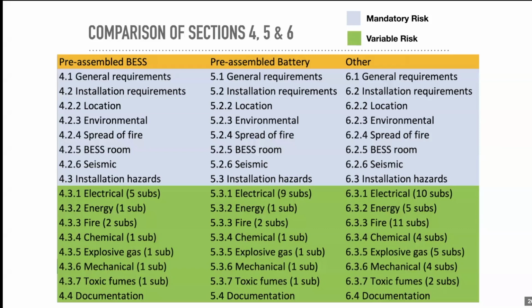The pre-assembled battery system, which is section 5 type, is really just a battery which has a, I should flag that pre-assembled BESSes are defined as lithium-ion batteries at the moment because they need to comply with the best practice guide as well. So to be in section 4, you've got to tick 2 boxes. You have to have a manufactured solution that includes the PCE, and that whole package has a manufacturer's declaration of compliance to the best practice guide.